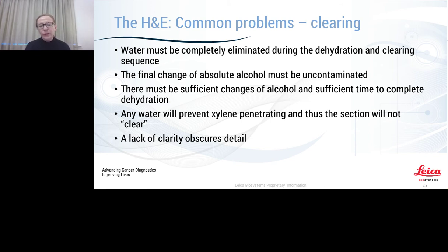Also remember your laboratory environment. Are you using xylene substitutes? Xylene substitutes will take on more water. Any alcohol will absorb water from the environment. So just make sure that you are aware of the humidity in your laboratory, and the storage conditions of alcohols, and make sure that you change at an appropriate time.